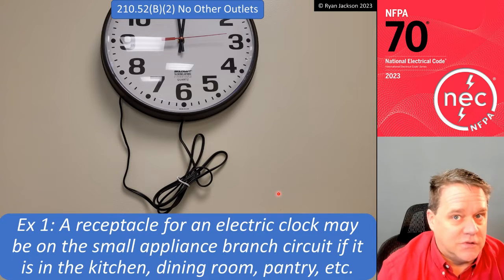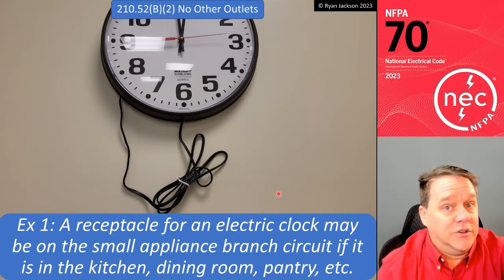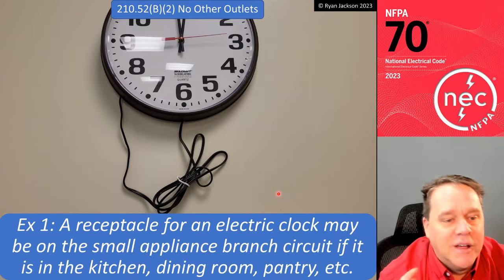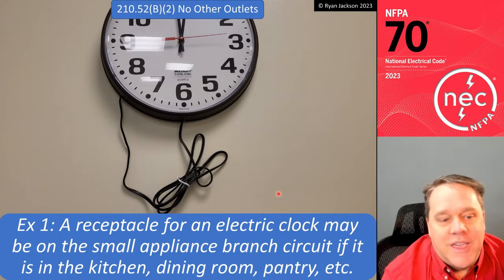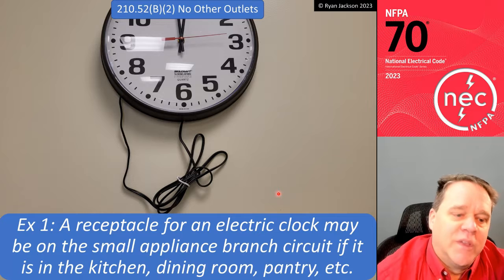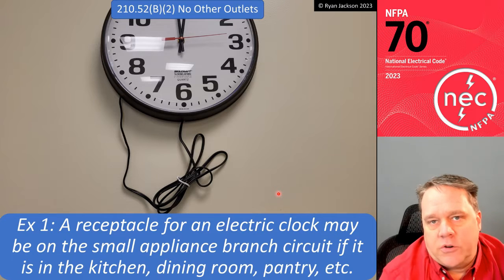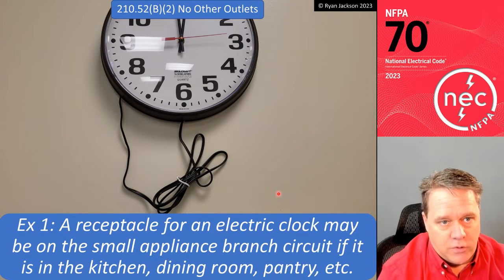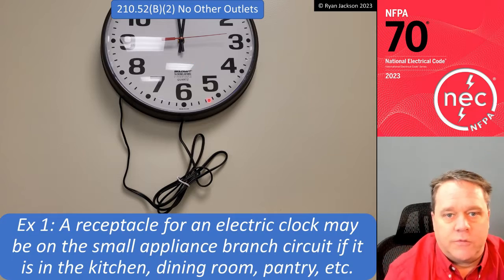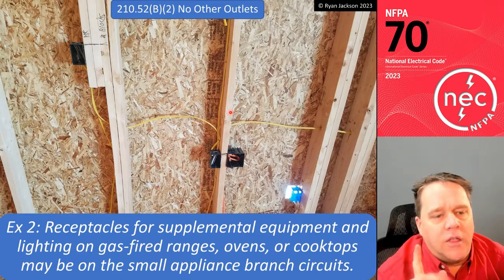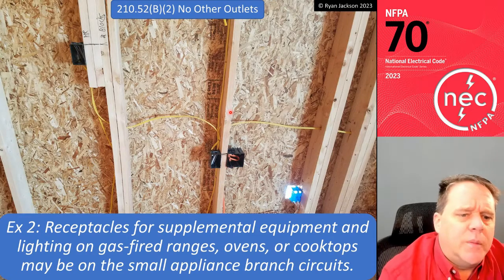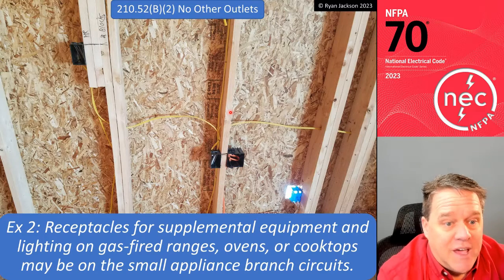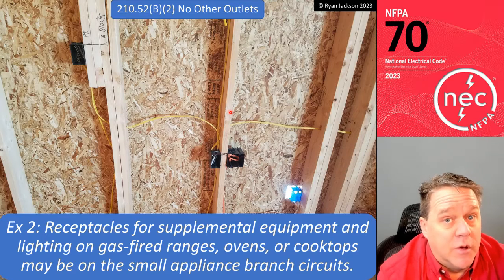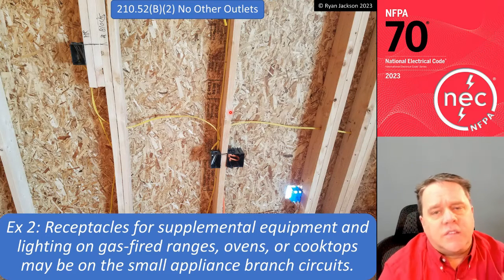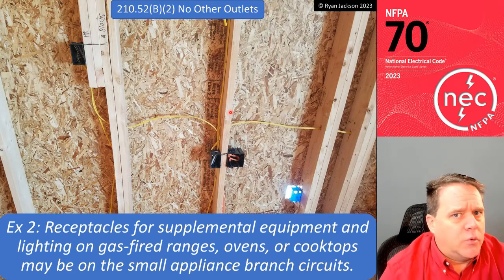If you have one of these, then I would tell you to join the 21st century. But a receptacle for an electric clock can be on the small appliance branch circuit if it's in the kitchen, dining room, pantry, etc. So, okay, fine. You want to have an individual receptacle for one of those, be my guest. The other exception, receptacles for supplemental equipment and lighting on gas-fired ranges, ovens, or cooktops can also be on the small appliance branch circuit. This is something that I saw get screwed up quite often.